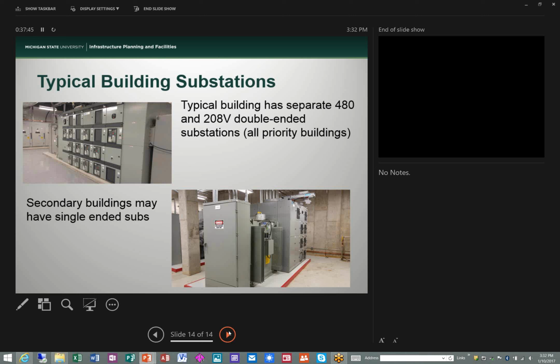Mm-hmm. This will be my last question before I ask Lauren. Lauren might want to pipe in. I notice here that you have liquid-filled transformers, which I think offers you some benefits in terms of size. Am I mistaken? You're likely to see a liquid-filled transformer smaller than a dry type of equivalent kVA. Right. Yeah, we've seen a lot of benefit from that. Your trade-off, though, is a different kind of maintenance issue, and because I'm so familiar with dry type, and we have them at our hospital, what kind of auxiliary air handling equipment do you need to move air out of your liquid-filled transformers? Are they less of a problem than a dry type would be?